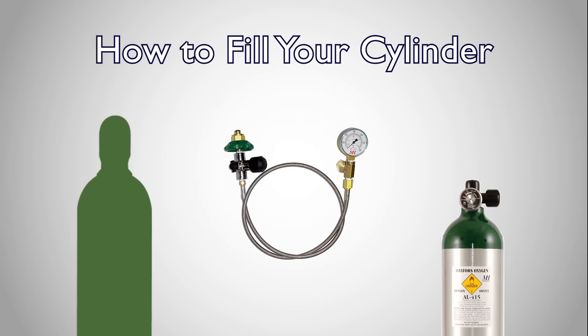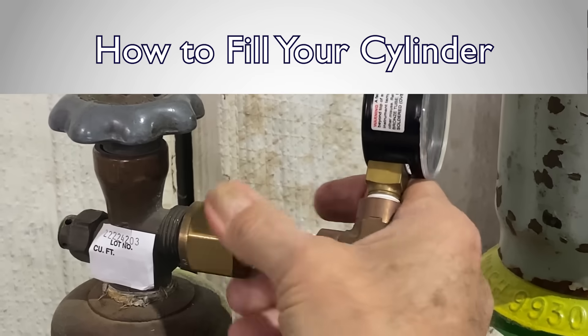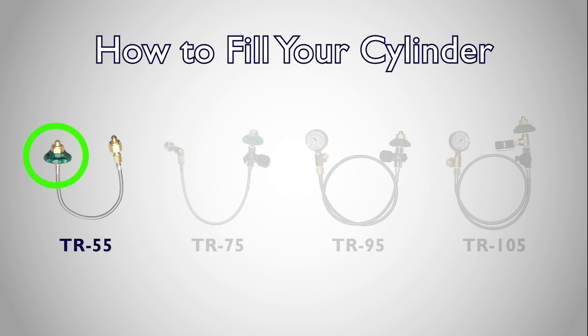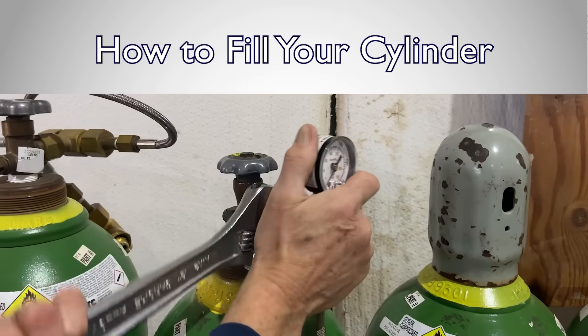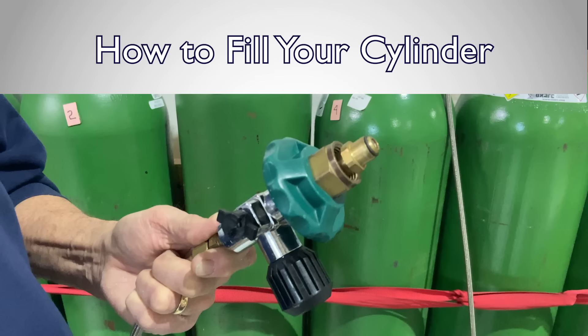Now let's fill your cylinder. First, connect the hose to the supply tank. For the TR75, 95, and 105, you will connect the brass hex side of the transfill hose to the supply tank. For the TR55, the green knob will connect to the supply tank — be sure to hand tighten it. With all of the other hose types, you may use a wrench to tighten the brass fitting; however the green knob should only be hand tightened.